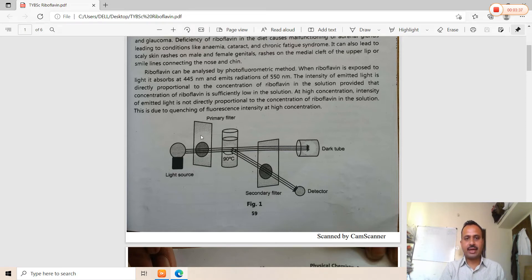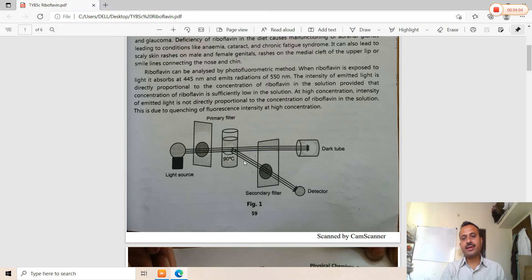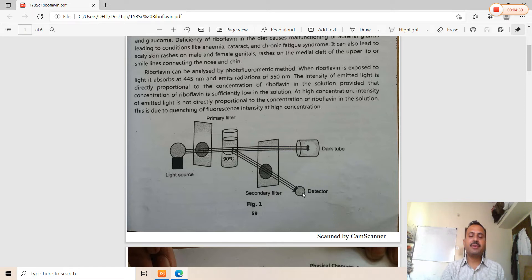Here is a block diagram of the photofluorometer. There is a light source, a primary filter, and the sample solution placed at 90 degrees. A secondary filter is also present. Light passes through the primary filter and is incident on the sample solution. On one side there is the sample cell, and on the other side is a detector. The radiation from the secondary filter is detected by the detector, which is connected to an amplification system and a readout control system.